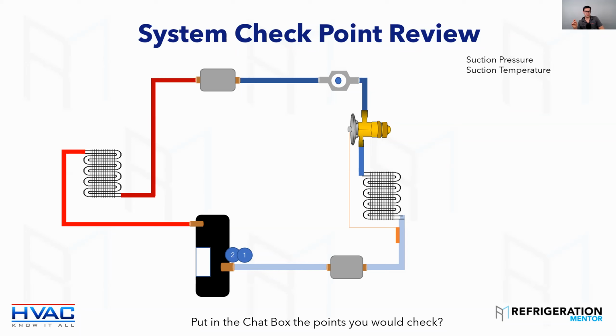Yeah, discharge temperature and pressure. High side pressure and temperature after a condenser for subcooling. Retro from R22 to MO99, adjust the TX for higher superheat. Well, you want to check with the compressor manufacturer, especially if it's in warranty. I doubt it's in warranty, because MO99 is not always approved for certain compressors. So it's always good to follow that up.